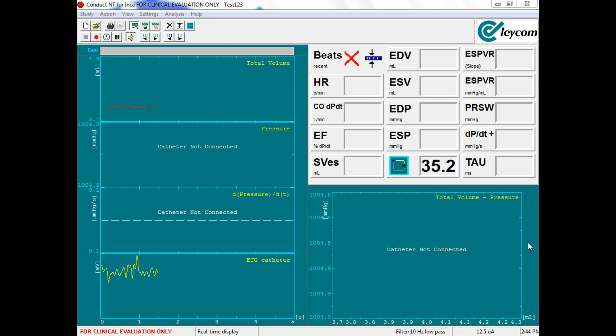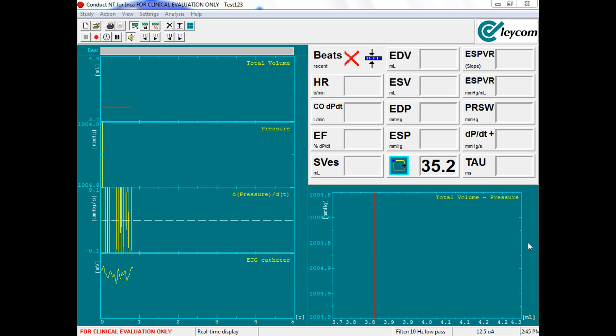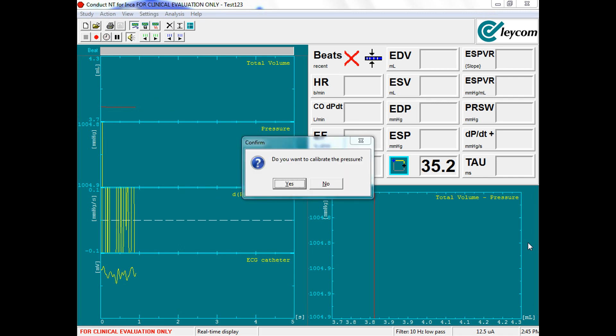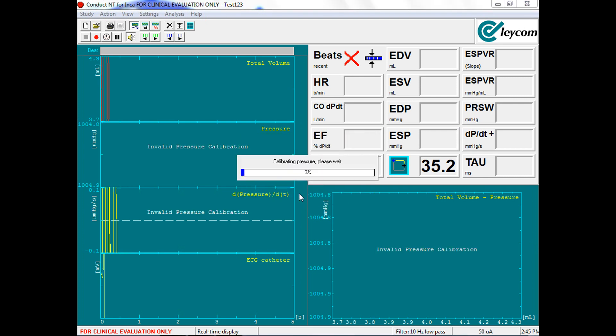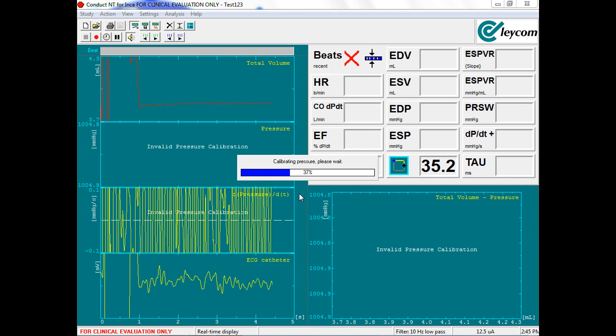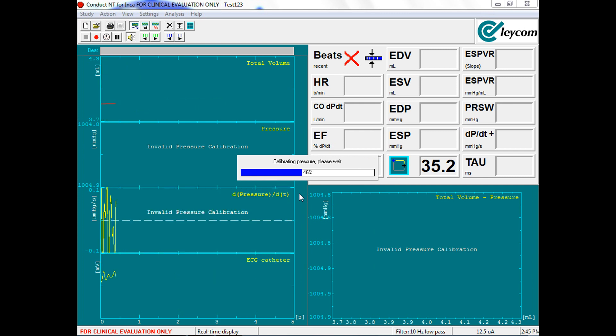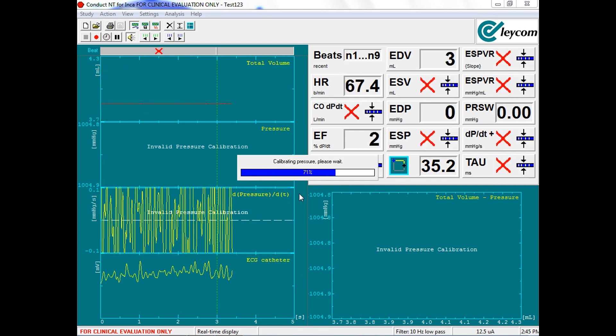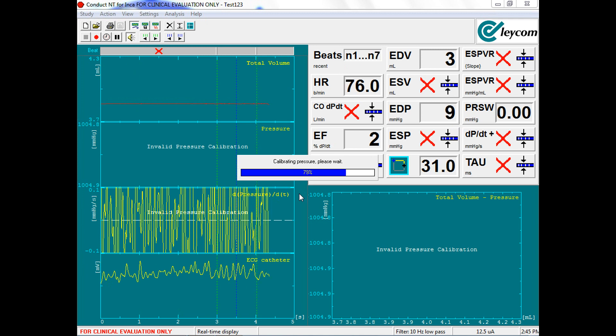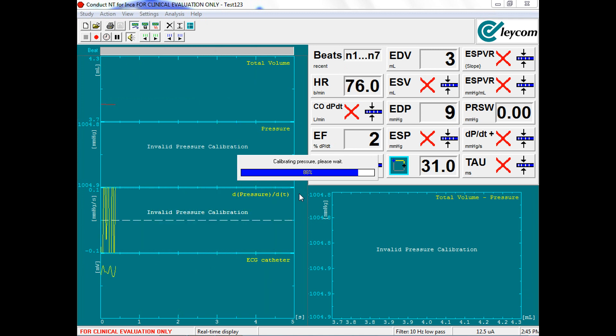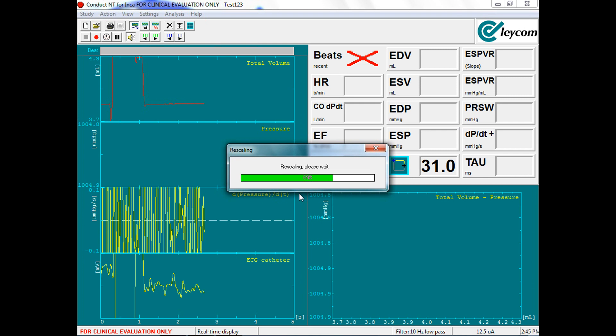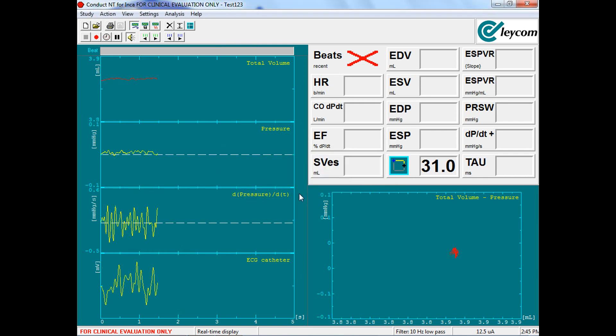Upon connecting the pressure cable to the INCA system, Conduct NT will prompt the user to calibrate the pressure signal. Click yes only after ensuring that the pressure sensor has been hydrated and the catheter is outside the body. Because of the electronic nature of CD Leycom's pressure sensor, one does not need to calibrate the pressure signal relative to patient height or orientation as is typical with a fluid-based pressure sensor. After the automatic pressure calibration has completed, the pressure signal will change from red to yellow confirming that this is a calibrated signal.